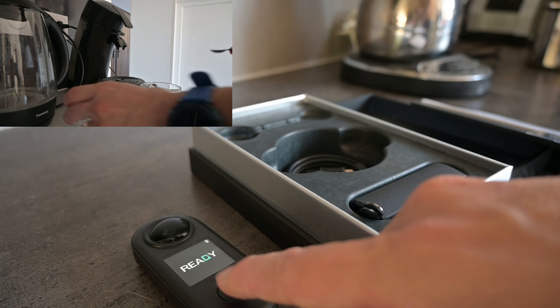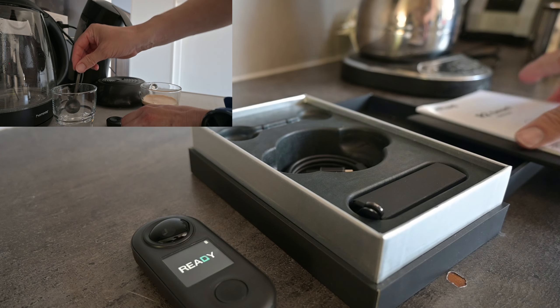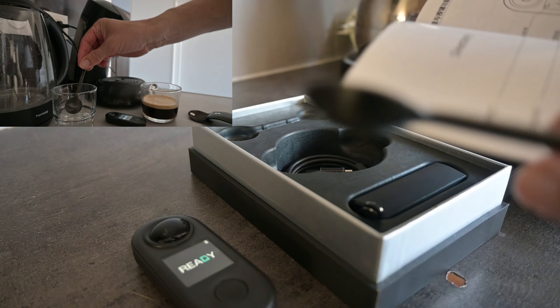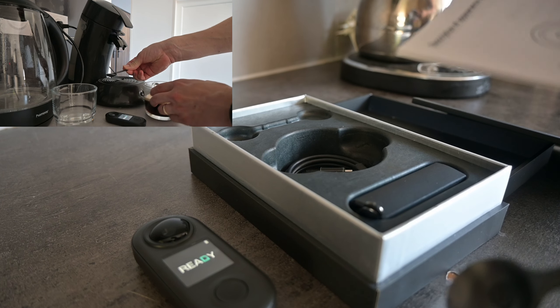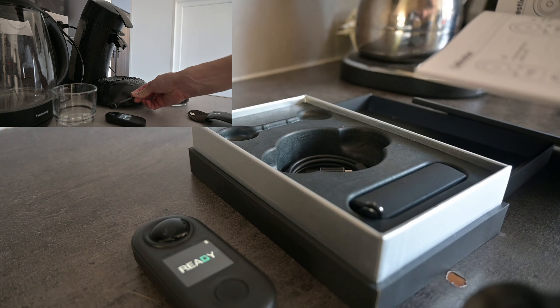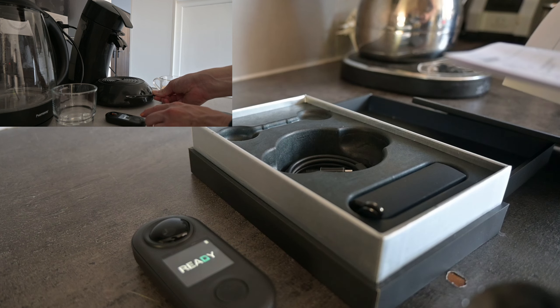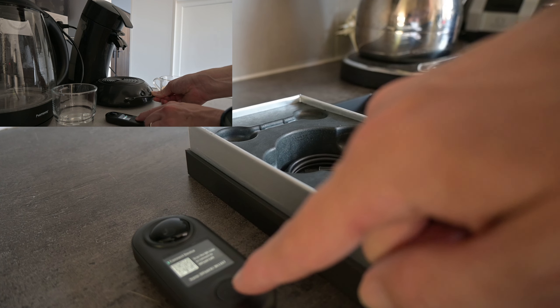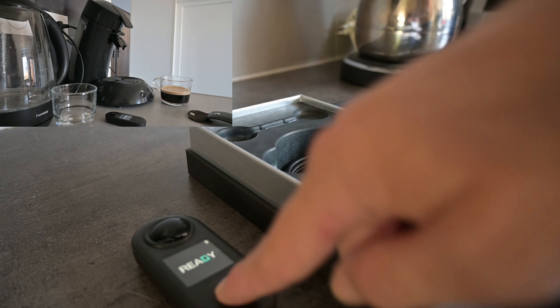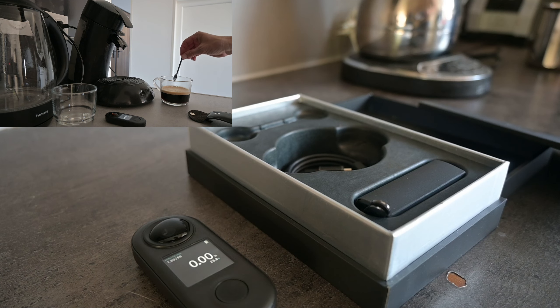The first thing you see here is zeroing the apparatus, and that already takes a little bit of figuring out. The device just says 'ready' when it starts, and to do a zeroing or calibration you need to give it one quick press and then keep pressing — it's like a double press situation. It's not clear how long you're supposed to hold it, and if you do it wrong you end up in a different menu, which you don't want.